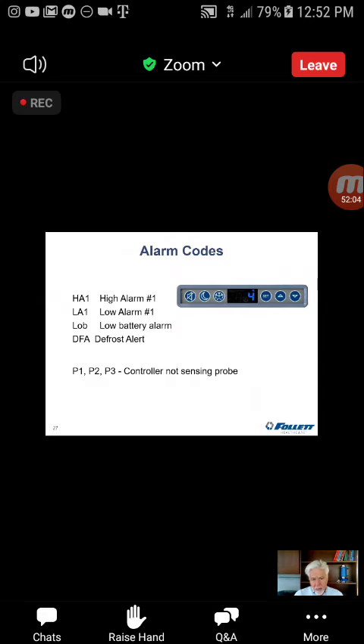Also, the board monitors the condition of the probes. If the board is getting a reading from a probe that makes no sense to it whatsoever, it will tell you which probe is the problem. It means that either it's not sensing, it's either open or it's shorted. There's something wrong with that particular probe, and it will let you know which one is the problem. So you can go right to it and figure out what's wrong there.